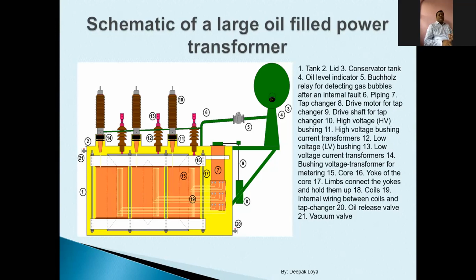To understand why cooling is required or why oil is required: oil first of all has better dielectric properties as compared to air. To reduce the clearances, we are using oil immersed transformers. Lower clearance is required because of the higher dielectric coefficient of the fluid as compared to air.